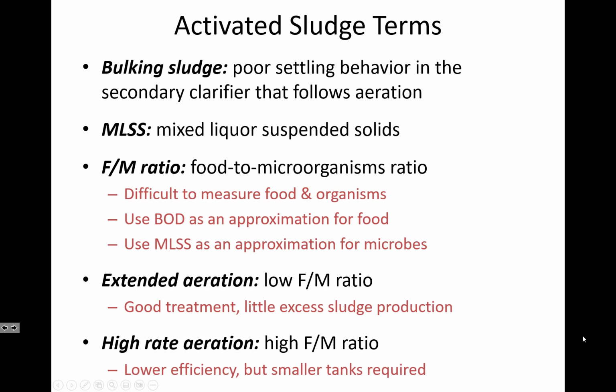There's something called the ultimate BOD, which is if you gave the microorganisms an unlimited amount of time, how much oxygen would they demand to break down the waste? And we don't often use ultimate BOD in monitoring the performance of a wastewater treatment plant because it would take maybe a month to determine what was the oxygen that was demanded. And 5 days is long enough to wait. So just a word that when we say we've measured the BOD, the secondary question is, over what time period did you measure the BOD? So we'll return to that topic a little bit later today.